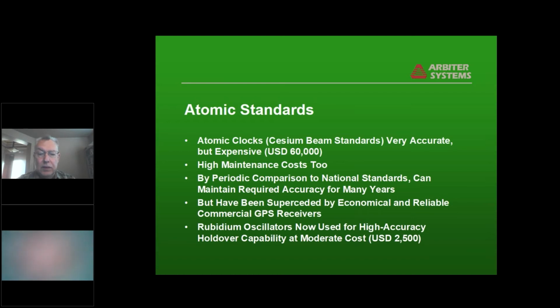Atomic standards are also usable. Cesium beam standards, which is what almost all of the members of the international timing community use, HP 5071, which I guess is now made by Symmetricom, which is a division of Microchip, was Microsemi, now Microchip. These things are very accurate, but they're also expensive, and every 5 to 7 years you have to put a new cesium beam tube in the thing, and those cost almost as much as a standard. That's the expensive part of it. So you're looking at several $1,000s a year to budget just to replace the cesium beam tube every so often.